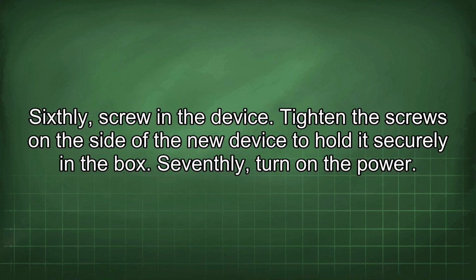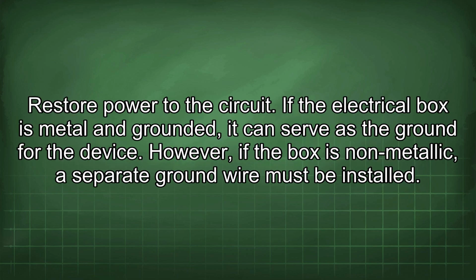Sixthly, screw in the device. Tighten the screws on the side of the new device to hold it securely in the box. Seventhly, turn on the power. Restore power to the circuit. If the electrical box is metal and grounded, it can serve as the ground for the device. However, if the box is non-metallic, a separate ground wire must be installed.